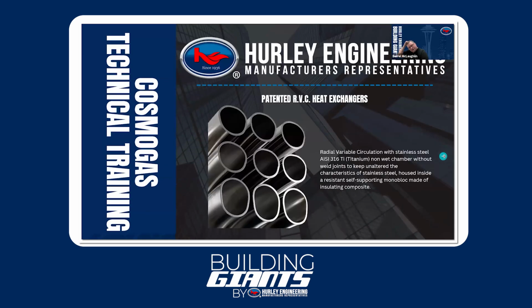So one thing I wanted to mention too, not just the parts kit, but the other, as far as the serviceability of this boiler. In order to keep the pressure drop low, this is not just one pass of tubes. Immediately upon entering the heat exchanger, the water is diverted, and there's actually 3 different runs of tubes in one pass. So what that means is, if you want to do a water side cleaning of the heat exchanger, we would need to be able to divert flow to each of these 3 paths. Well, CosmoGas has a manifold.